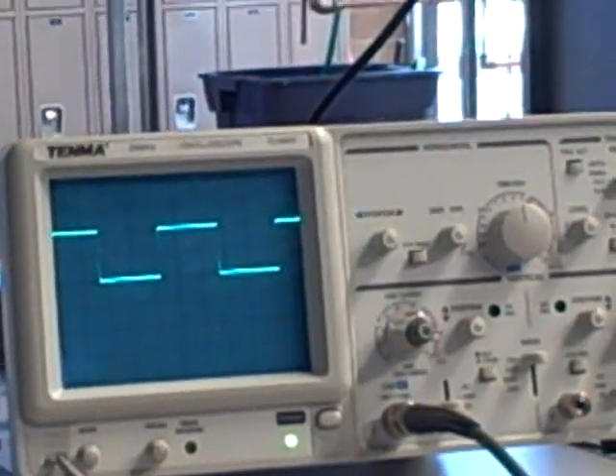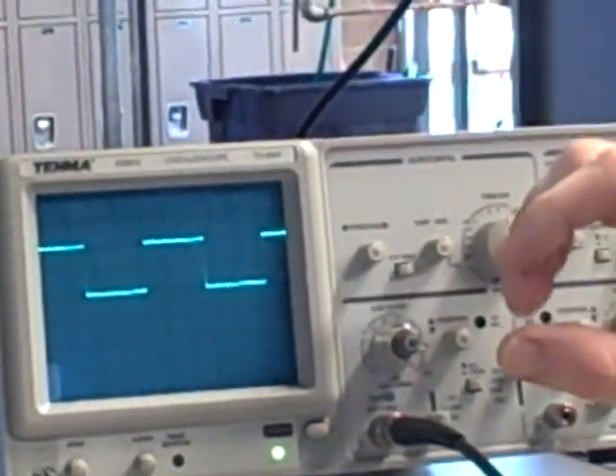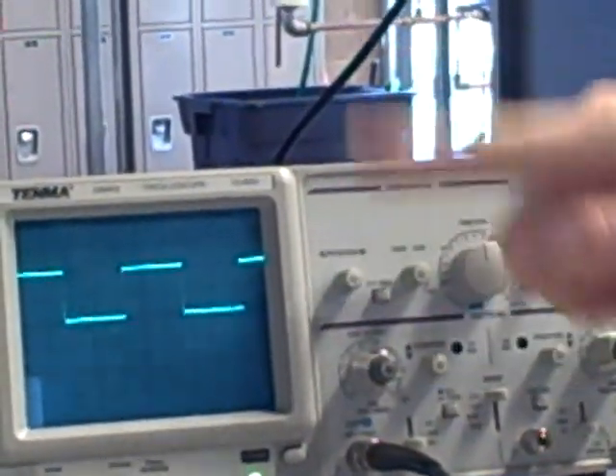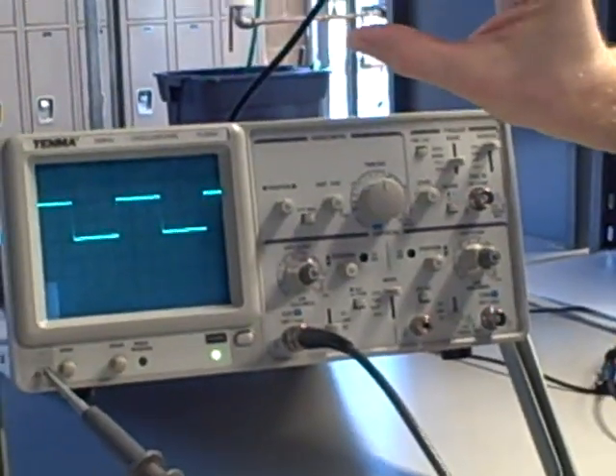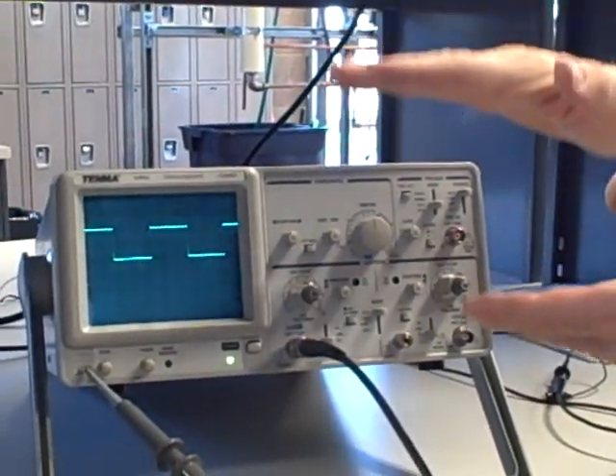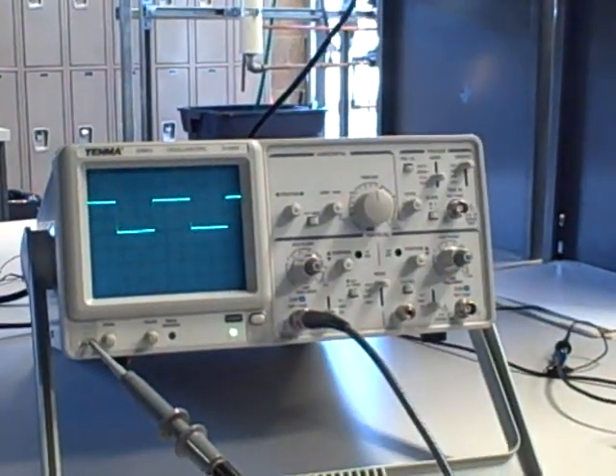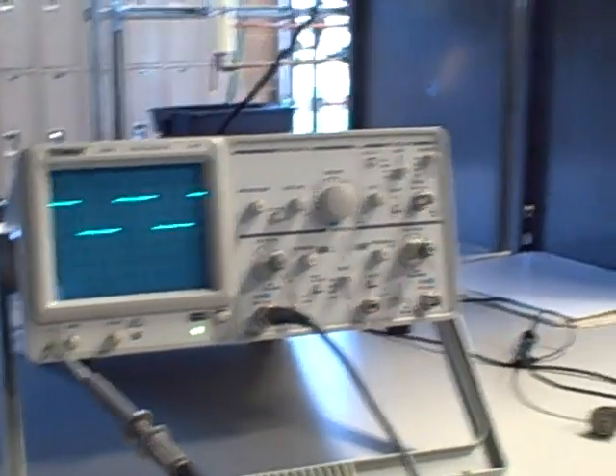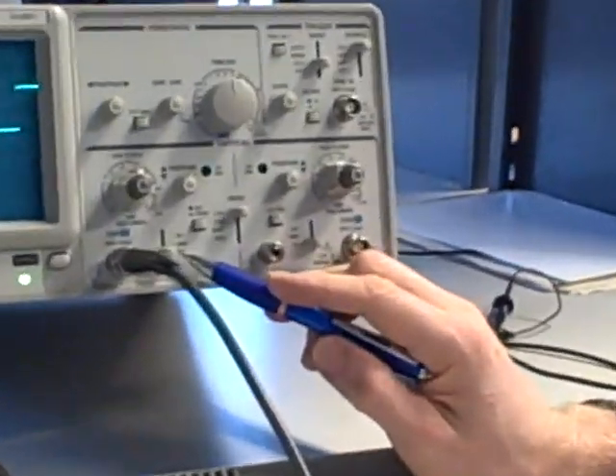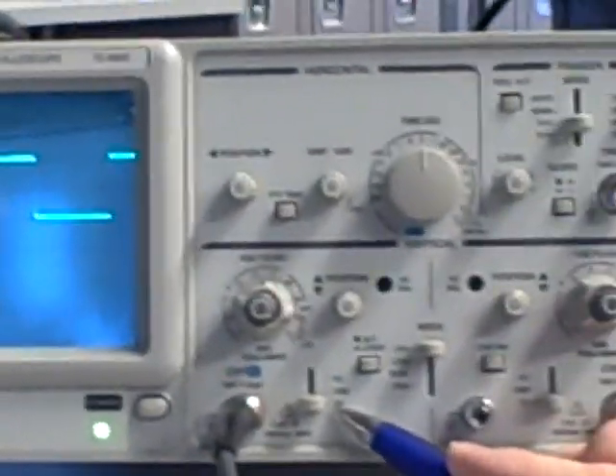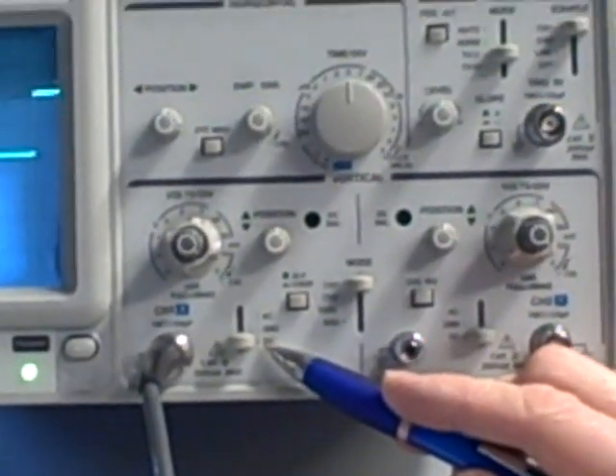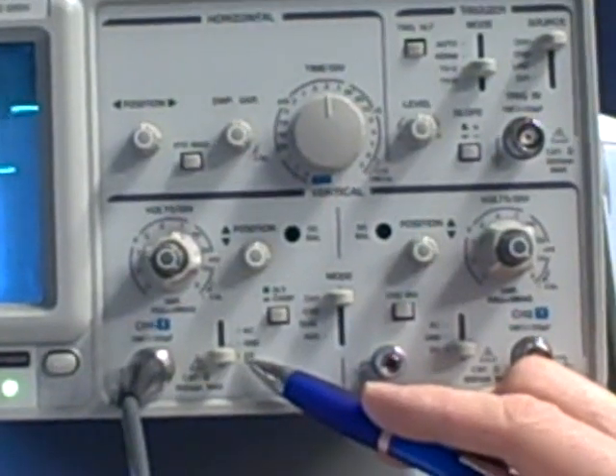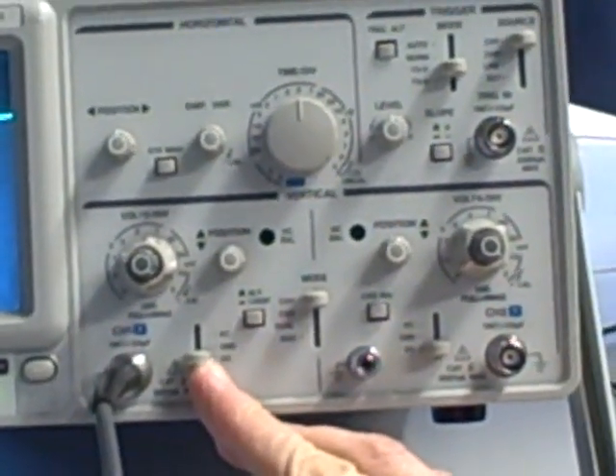Now there may be times that I want this oscilloscope to automatically center the wave. In other words, let's say I have a waveform that's going up and down, but that entire waveform is elevated or biased with a DC voltage. There may be times I want to get rid of that elevation and just show the waveform itself, the oscillating part centered around the screen. And if I want to do that, the way I do so is I use this control down here. This is called my coupling control. Currently it's set on DC coupling, which is the same thing as an amplifier circuit that has DC coupling between stages. DC signals pass through unhindered.